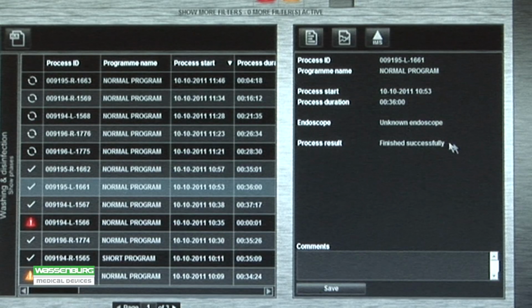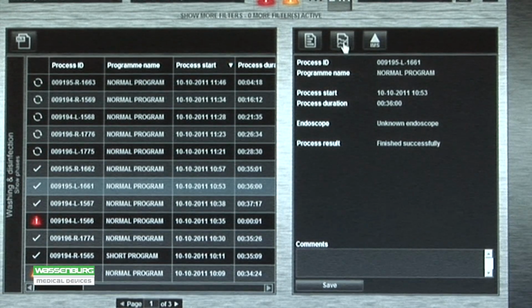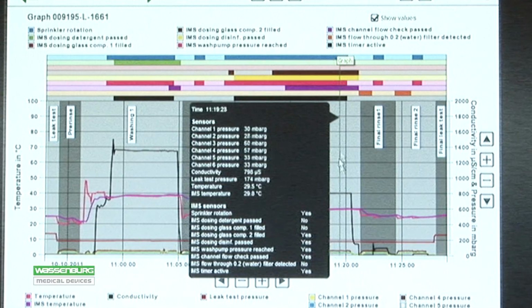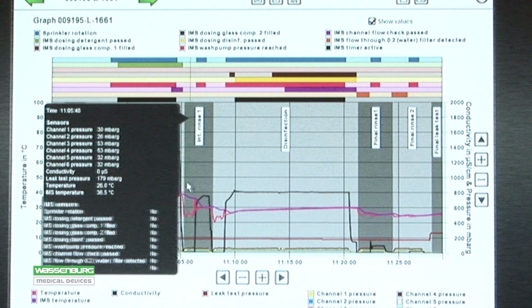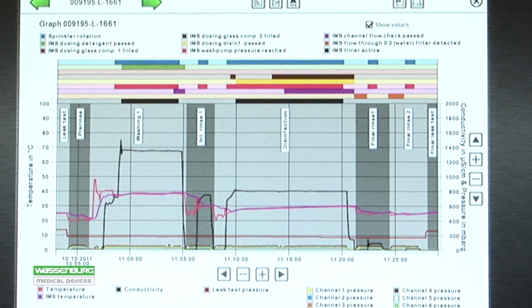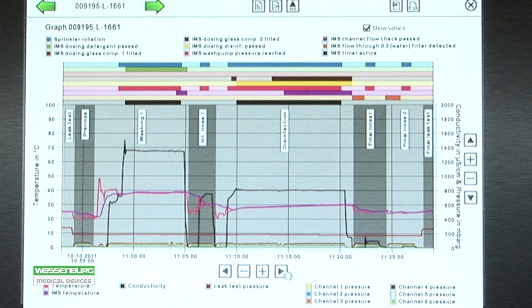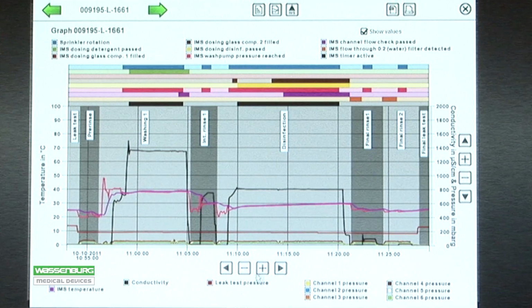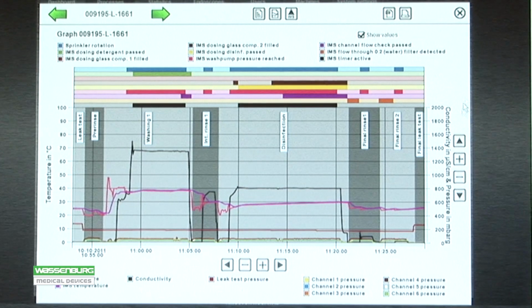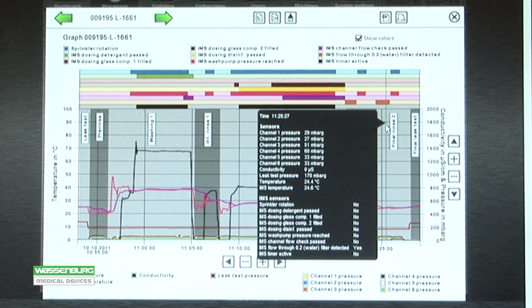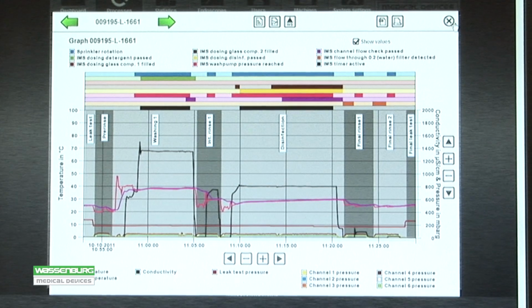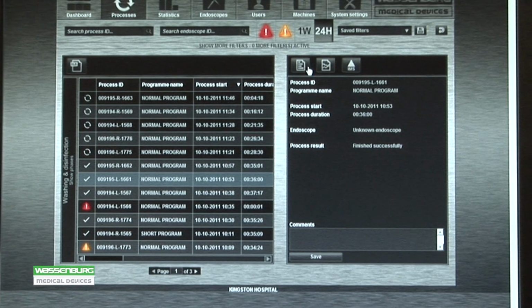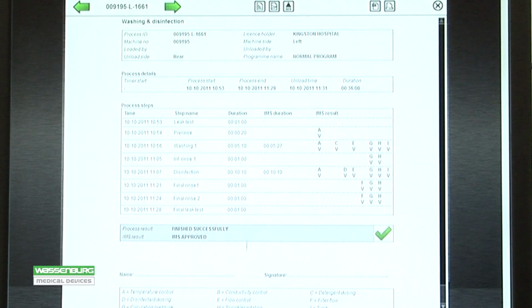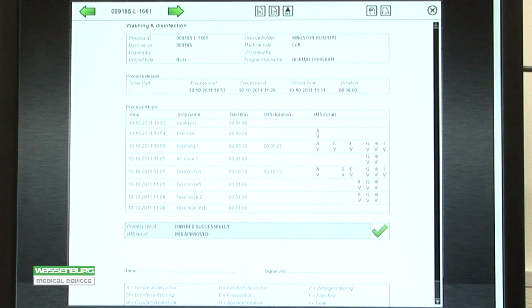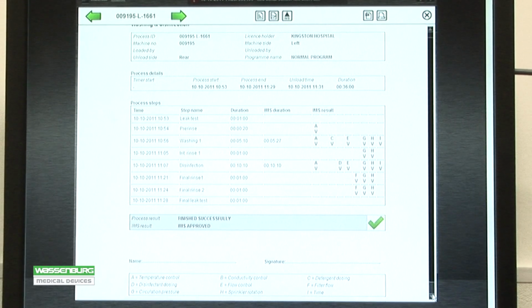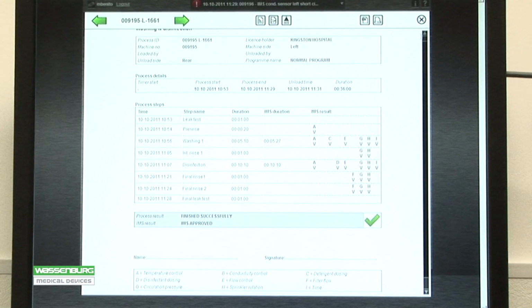The Process Manager system data is stored on the hospital server and each item of equipment is allocated an IP address to interface via the network using RJ45 connections. All hospital scopes are identified on the system by barcode number with trained operator identifications. Operators can therefore access scopes from any machine, including those remote from the day surgery unit, in theatres or endoscopy department Dry 300 cabinets, as data is accessed centrally from the server.